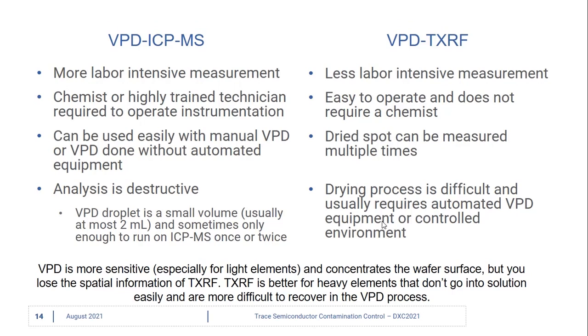VPD as a wafer surface sampling technique is more sensitive overall, especially for light elements, and concentrates the entire wafer surface. But we lose the valuable spatial information gained from direct TXRF. Direct TXRF is also better for heavy elements like ruthenium and gold, which don't go into solution as easily and are more difficult to recover in the VPD process.